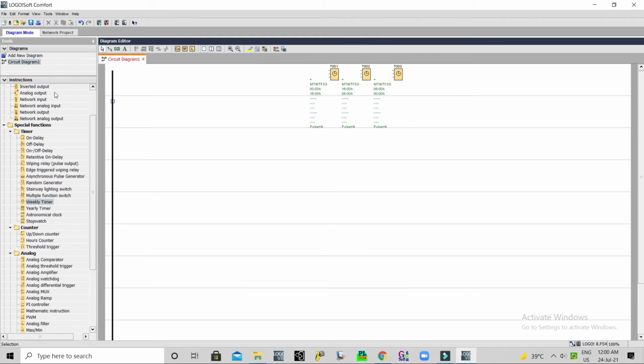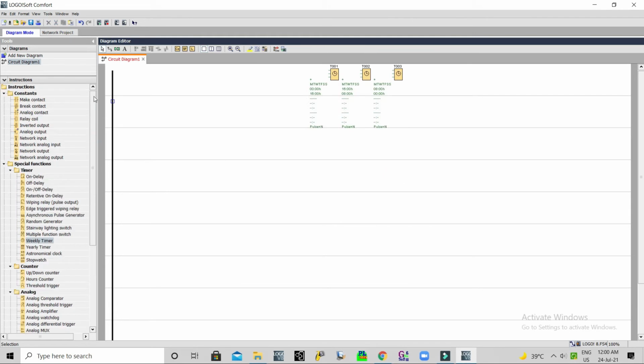Now we will make the program. We have 4 inputs: three auto signals, one from each AC, and one from the room high temperature thermostat. This thermostat will sense the room temperature. When it reaches the set high temperature value, it will give an input signal to the controller, so the controller will work accordingly.